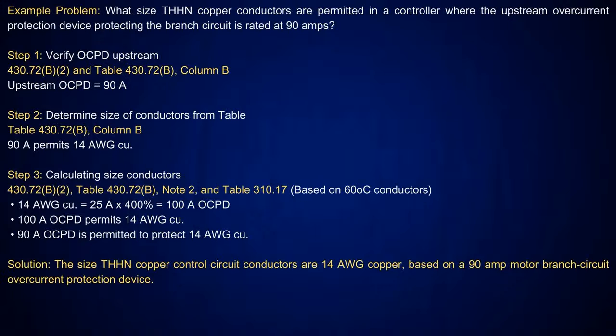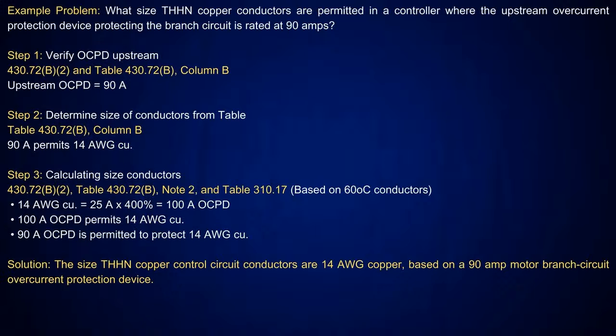Okay? And if you look at the bottom of the table, it's going to tell you that it's based on table 310.17, and I'm going to use a 60-degree C column. So when you go over and look at table 310.17, you pick up the number 14 copper conductor. It's going to tell you it's good for 25 amps. But right below that table, in note 2, it's going to tell you take it at 400%. And if you take 400%, that gives you 100 amps. See that? Right. Which permits the number 14 conductor. Therefore, that 90 amp is permitted to protect those number 14 conductors.